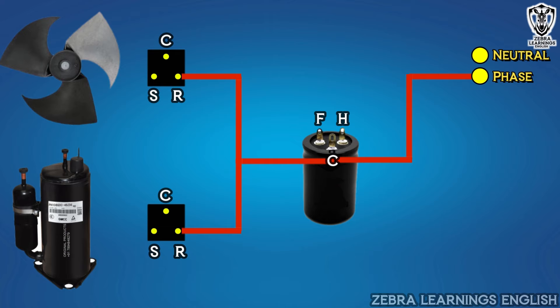Then, connect from the fan terminal of the capacitor to the starting terminal of the fan motor. And from the herm terminal of the capacitor to the starting terminal of the compressor.